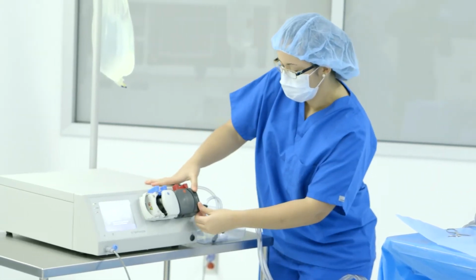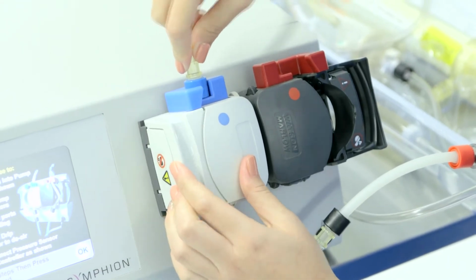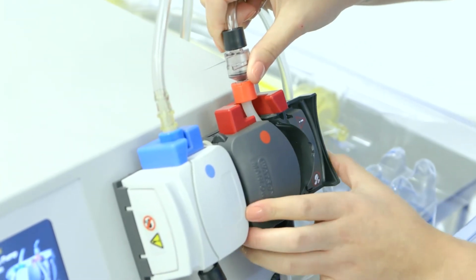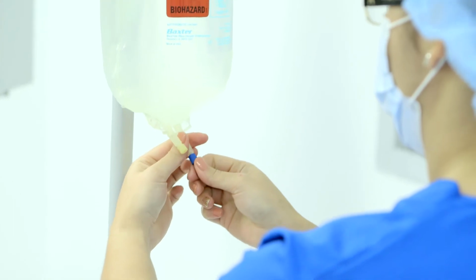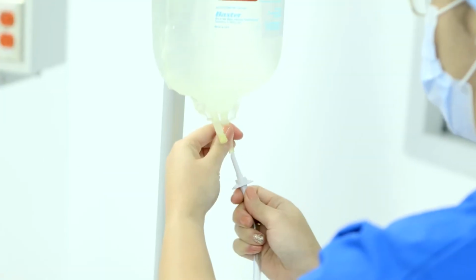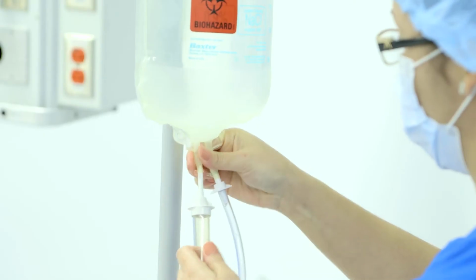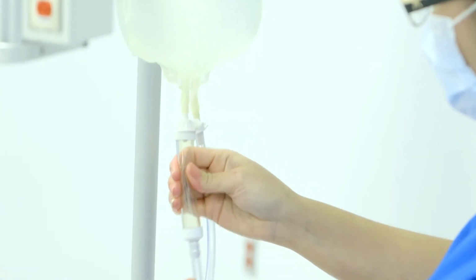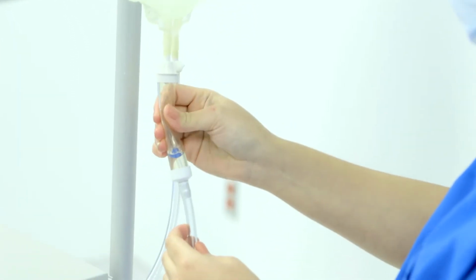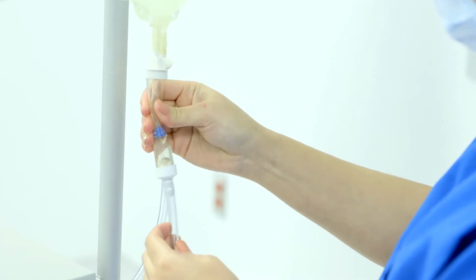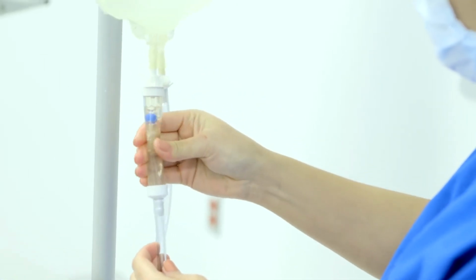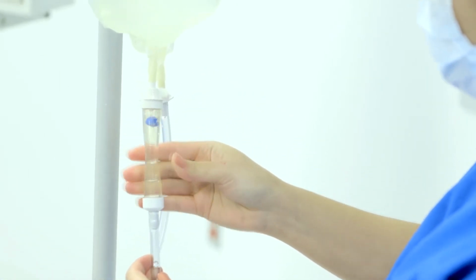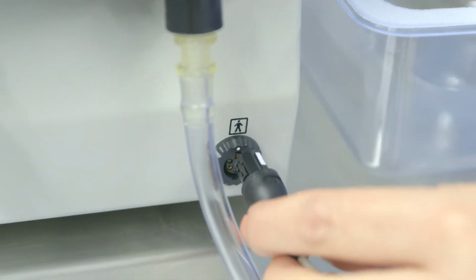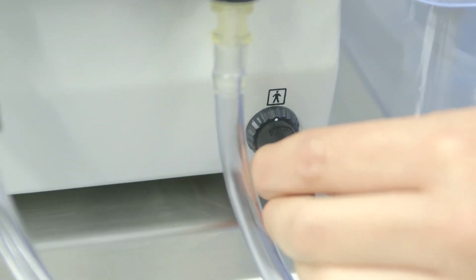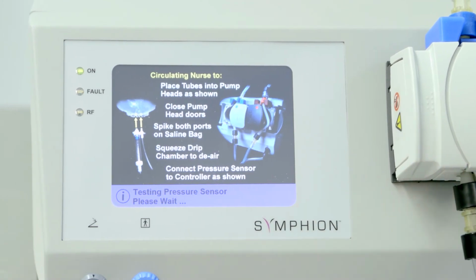Insert the infusion and aspiration tubes into the corresponding color-coded pump heads. Remove caps and spike both ports of the saline bag. Repeatedly squeeze and release the drip chamber at the end of the infusion tube until it is completely full of saline and the blue ball is at the top of the chamber. Connect the pressure sensor to the controller. Press OK on the controller screen to proceed.